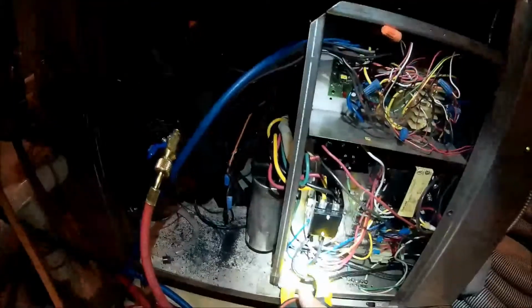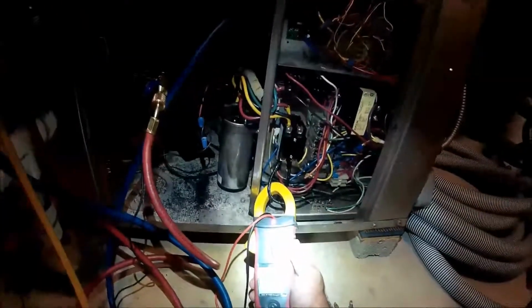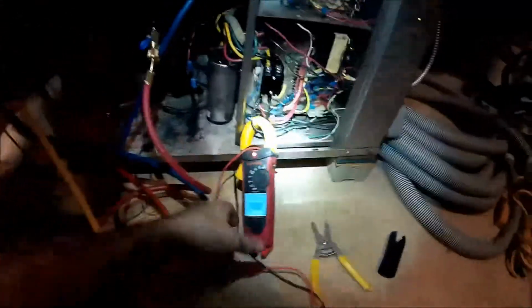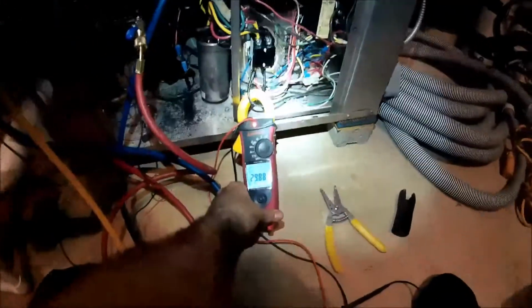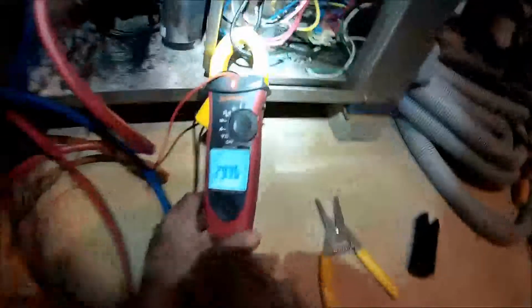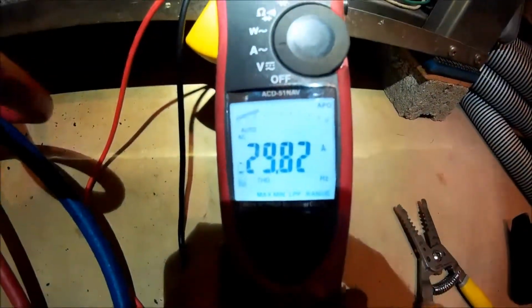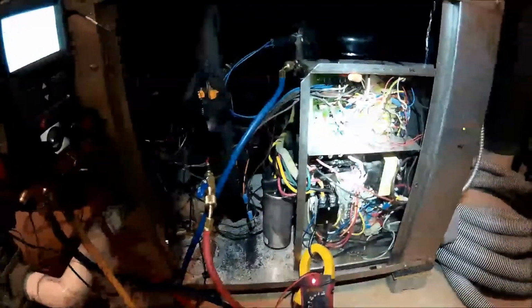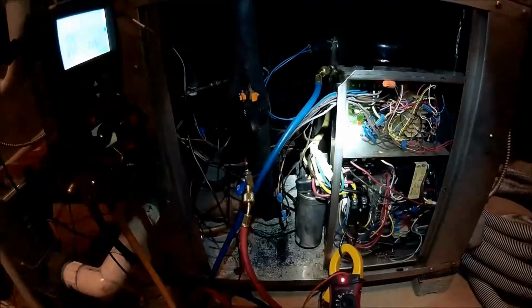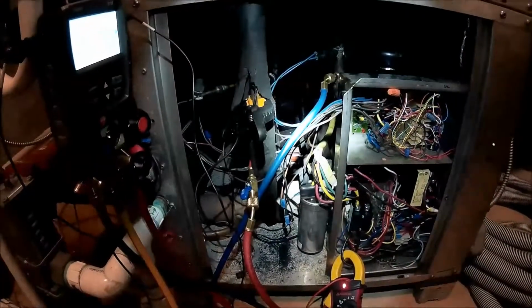Thermostat went bad, wasn't energizing the fan circuit, so the fan would come off, and it went off on low pressure. Right now I got a system at 29 amps. It's running okay, it's cooling, but I don't think it's running the way it should. Like I said, it's probably overcharged.